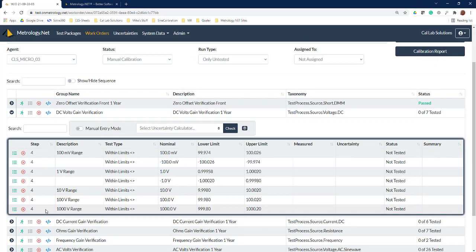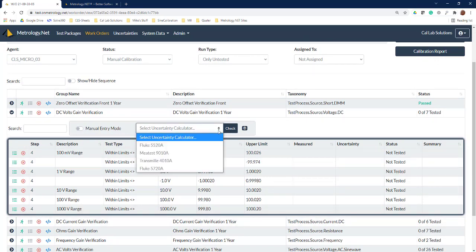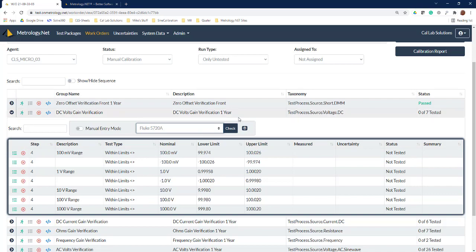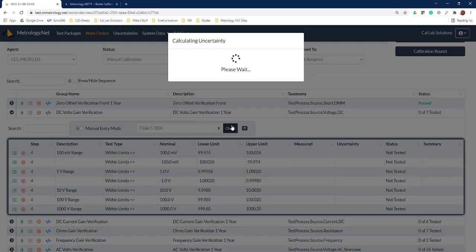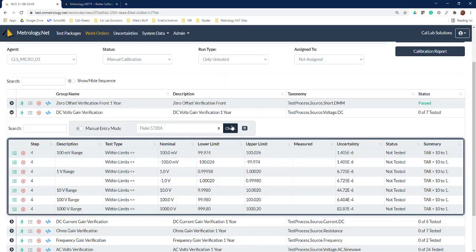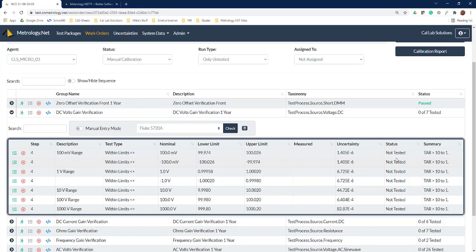We can see we've got some data points here that we need to collect. So we want to see can I do this work with a 5720? I can do a check—it's going to calculate the measurement uncertainties for each one of the data points and give us a TAR test accuracy ratio of 10 to 1. We can't do measurement uncertainty yet because we don't have repeatability and resolution, so all we're doing is comparing the accuracy ratios between the two standards.